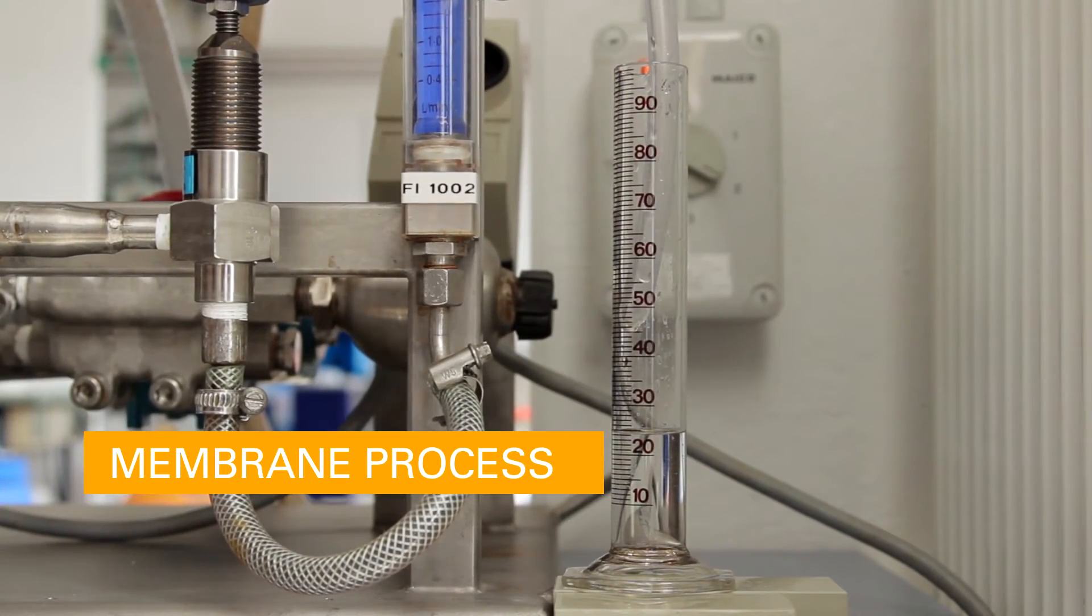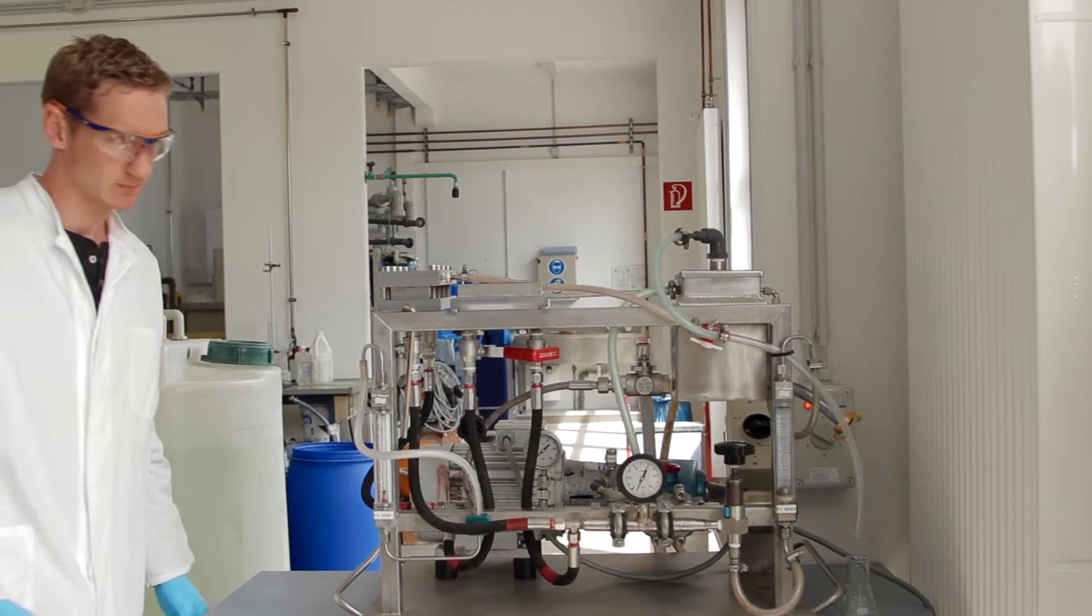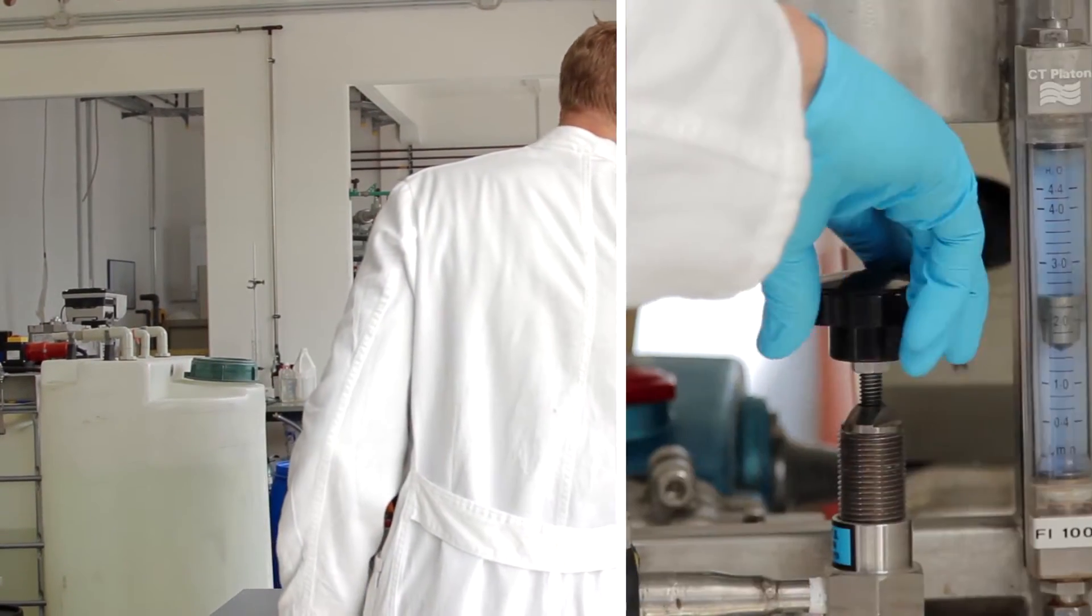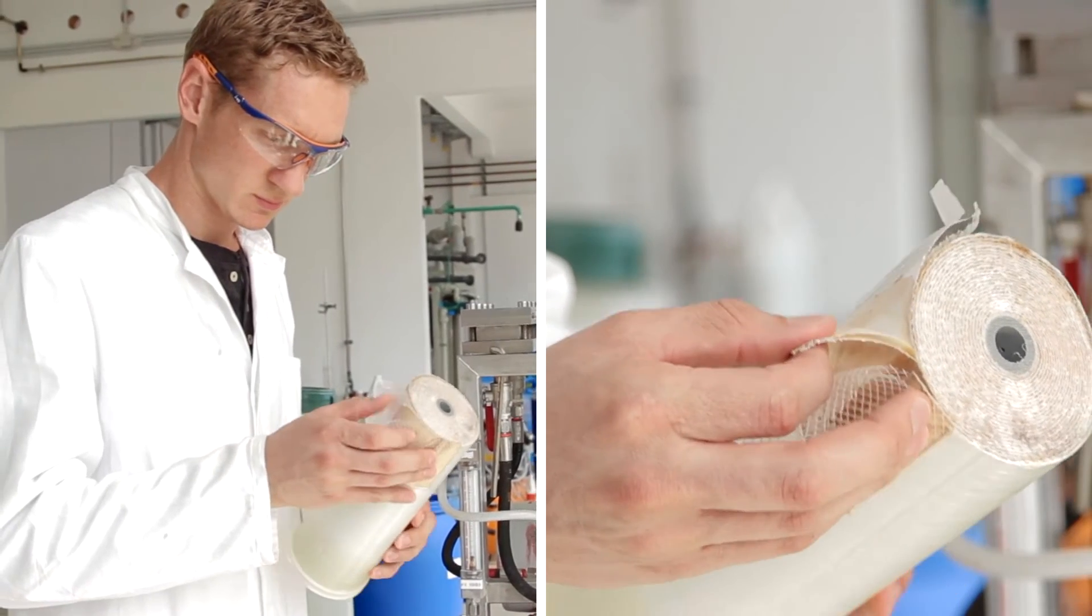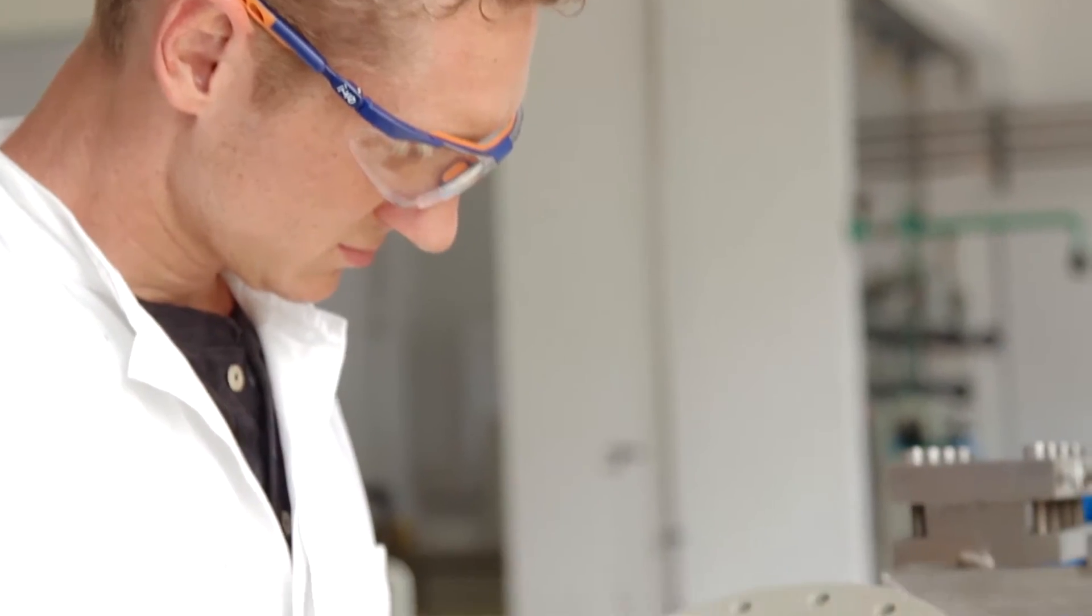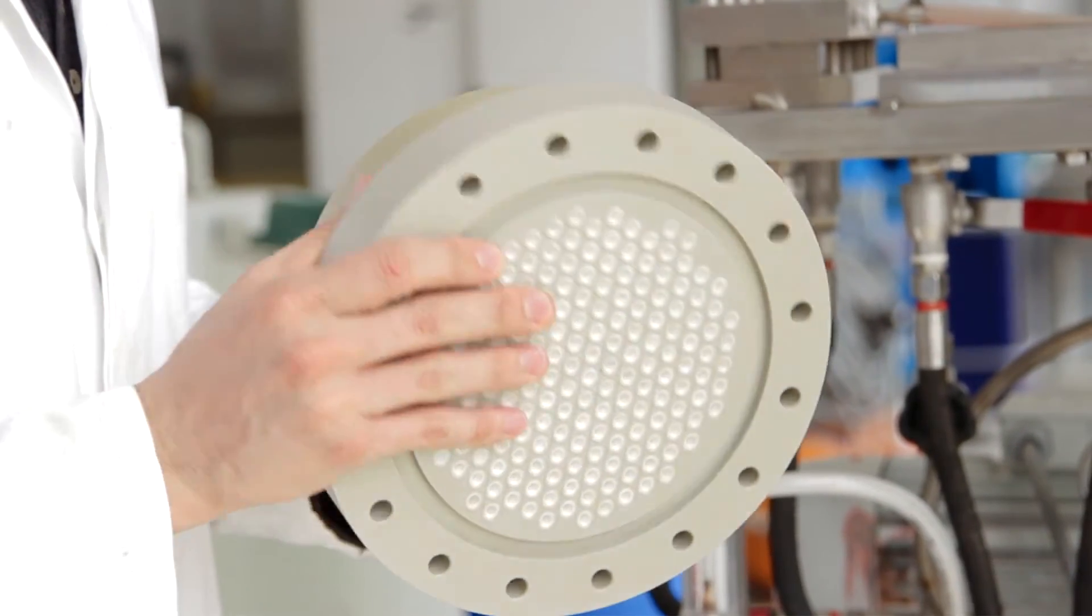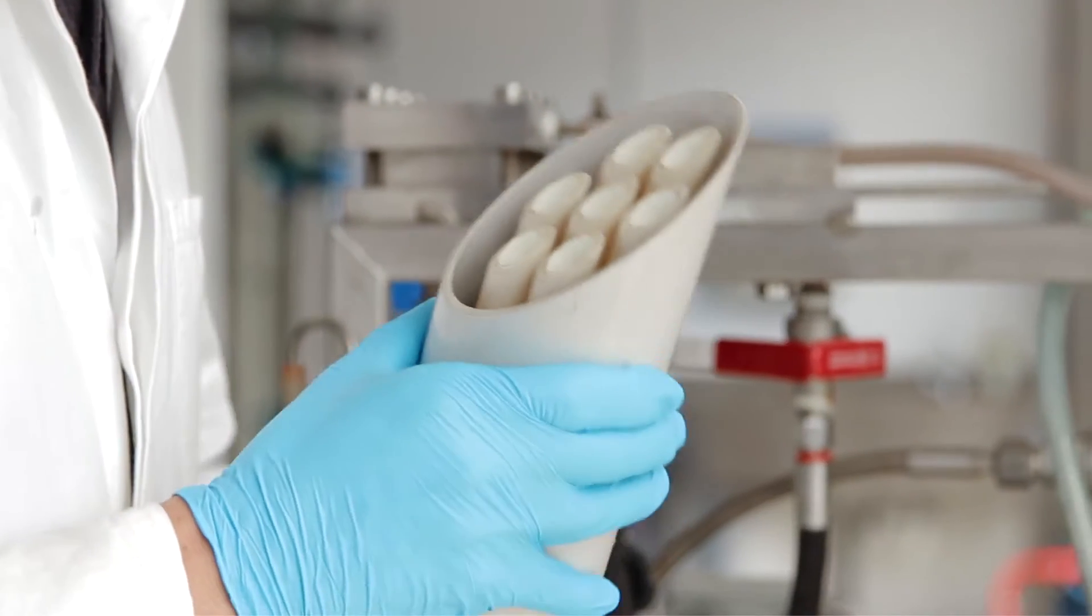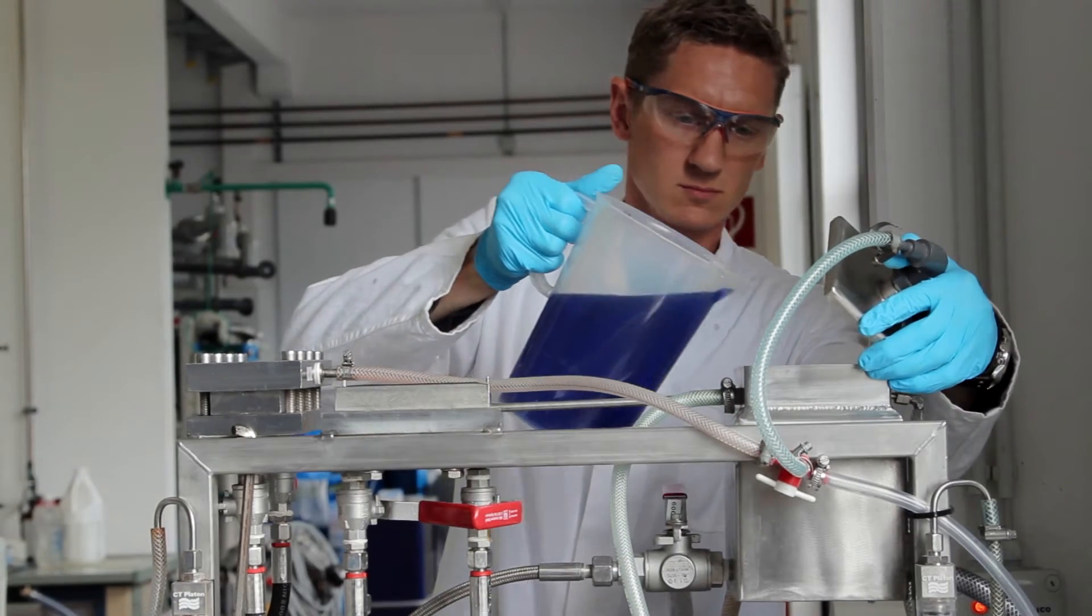Membrane process: The membrane process filters dissolved and undissolved substances out of the wastewater. The pore size of the membrane determines which molecules can pass through it. Different membranes are used in order to achieve the desired purification performance. Typical membrane processes used for water and wastewater treatment are microfiltration, ultrafiltration, nanofiltration, and reverse osmosis.